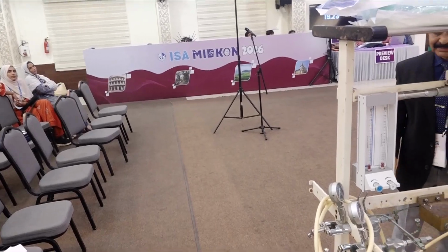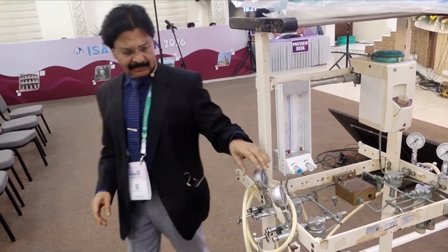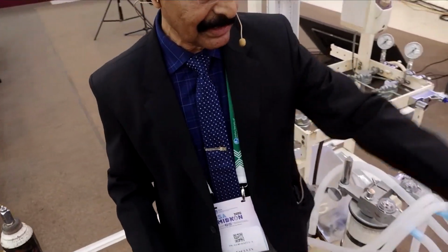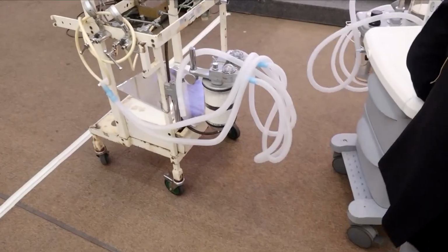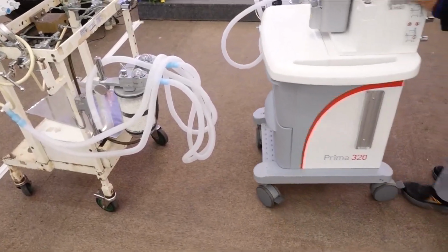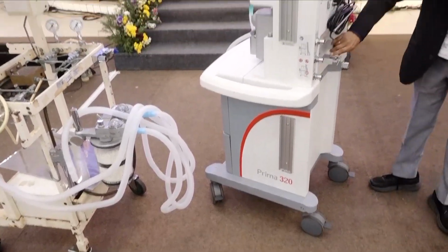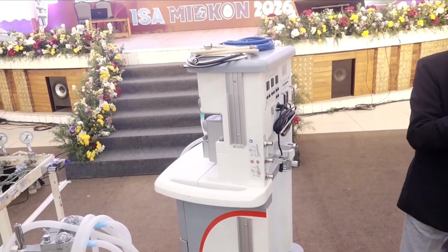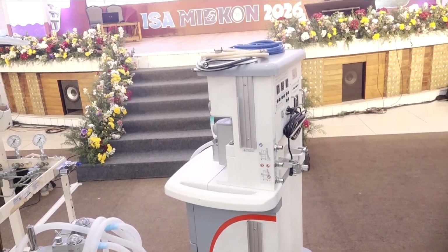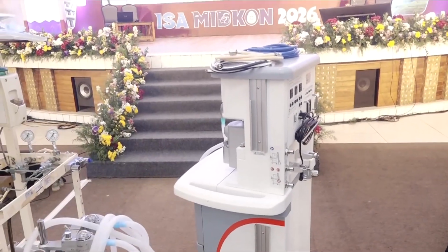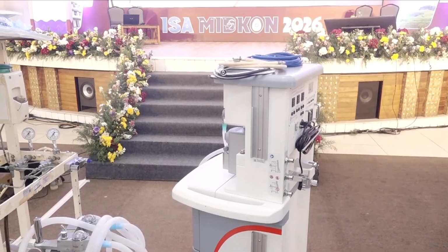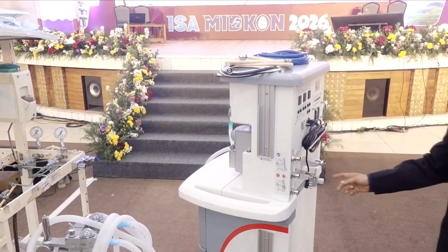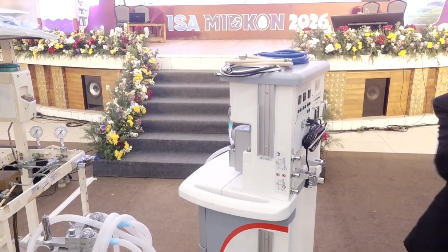Another very important thing here is that there will be unidirectional valves inside the yoke assembly. We have the yoke assembly on the workstation also, so you have to know about it. These are the yoke assemblies. Inside the yoke assembly, you have a unidirectional valve, and this valve will make sure that the gases only flow towards the machine and not away from the machine. But many times these unidirectional valves may not be functioning properly.